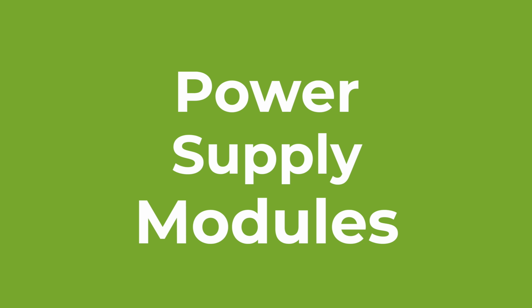Still staying in the back of the chassis, we also have the power supply module, the PSMs, or PSU for power supply units. These PSMs are both a consumer and a provider of energy. Consumer because they contain a fan. So depending on the sensors, it will operate at a different speed and consume more or less energy. The main job of the PSM is to convert the current provided by the grid, like 220 volt AC or 48 volt DC, into something usable by the router cards and components. Usually it's a 12 volt DC feed, but some systems may need different voltage, like 52 volts.